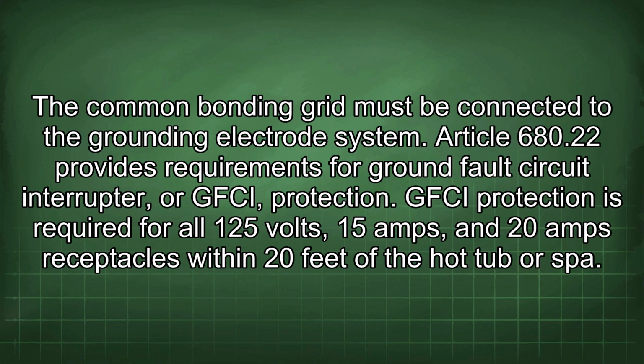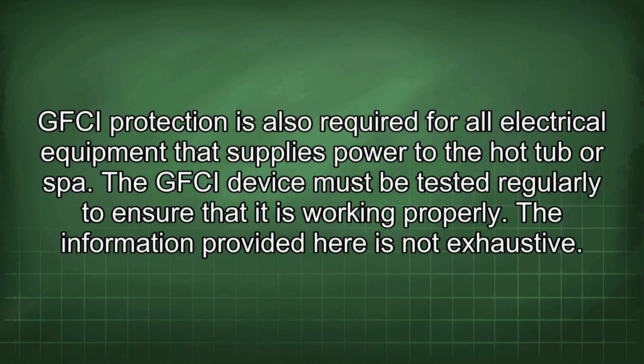Article 680.22 provides requirements for ground fault circuit interrupter, or GFCI, protection. GFCI protection is required for all 125 volt, 15 amp and 20 amp receptacles within 20 feet of the hot tub or spa. GFCI protection is also required for all electrical equipment that supplies power to the hot tub or spa. The GFCI device must be tested regularly to ensure that it is working properly.